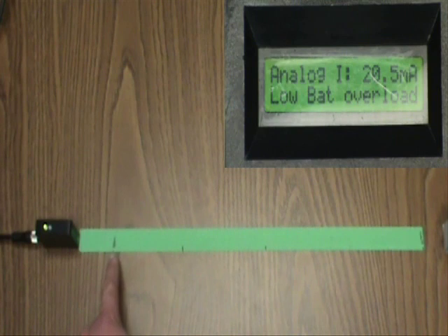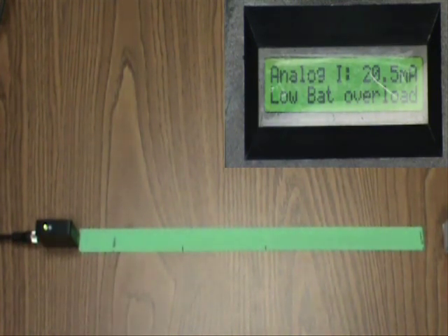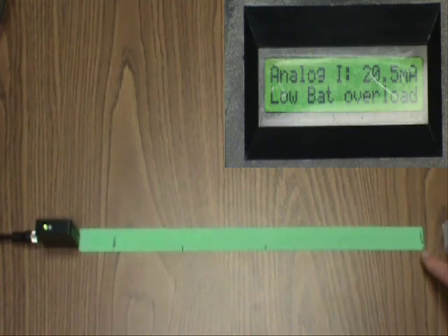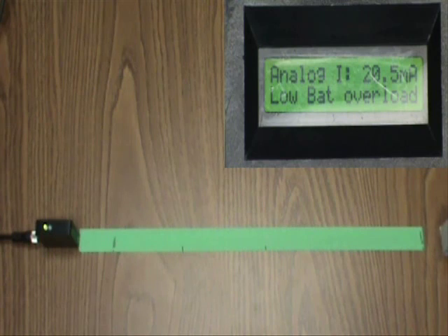In this example, we are still looking at the minimum distance of 50mm all the way to the maximum distance of 500mm. As the current position of our object rests, we are currently outputting 20.5mA.